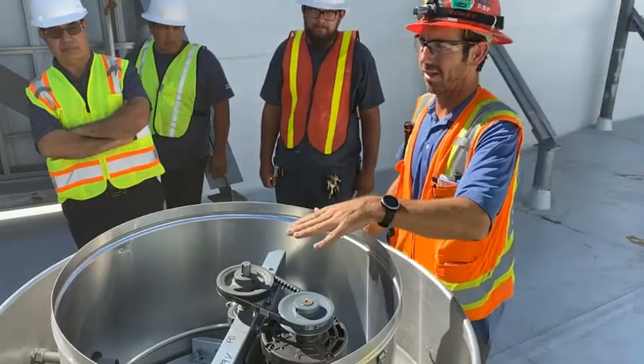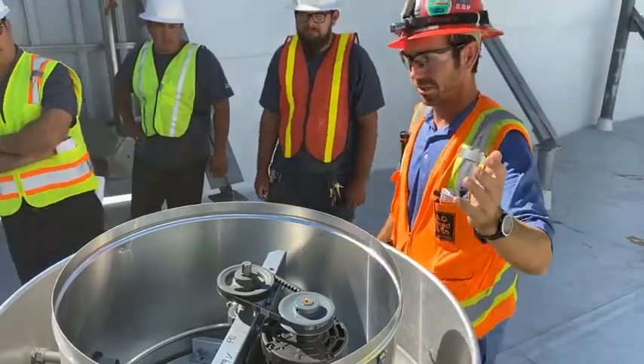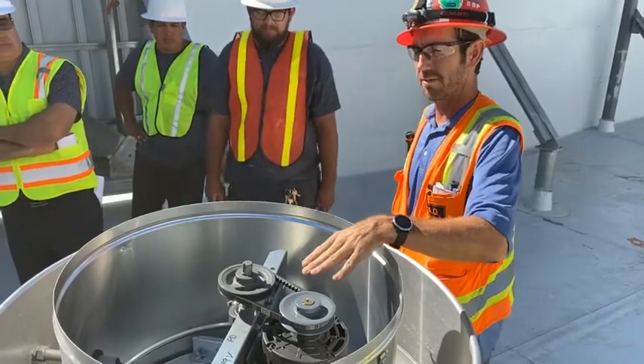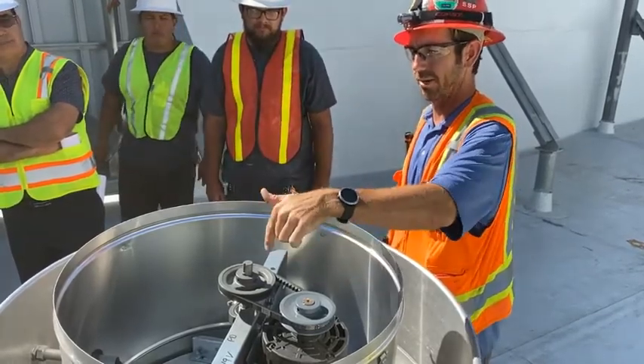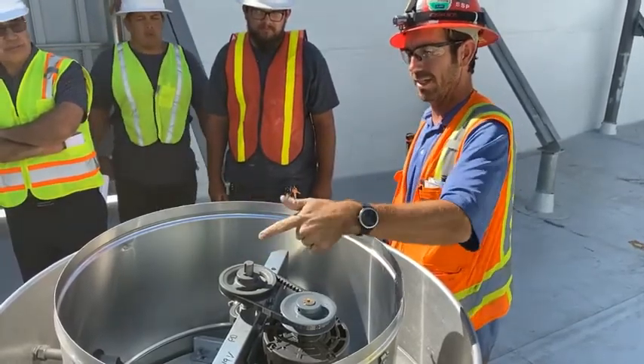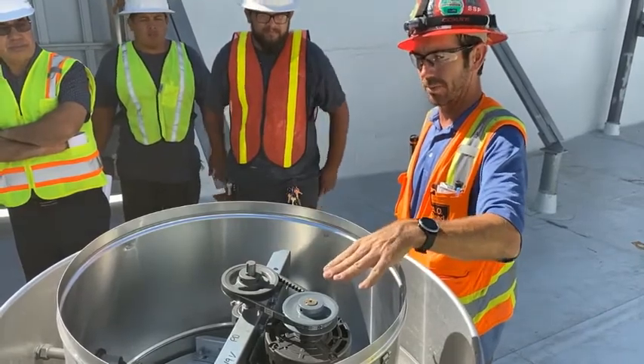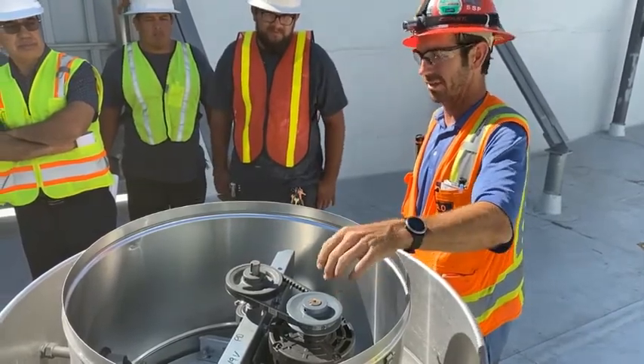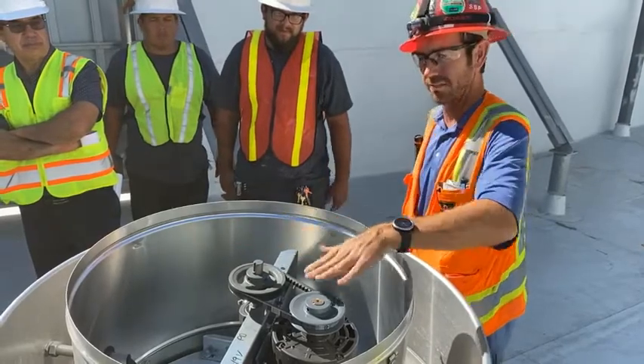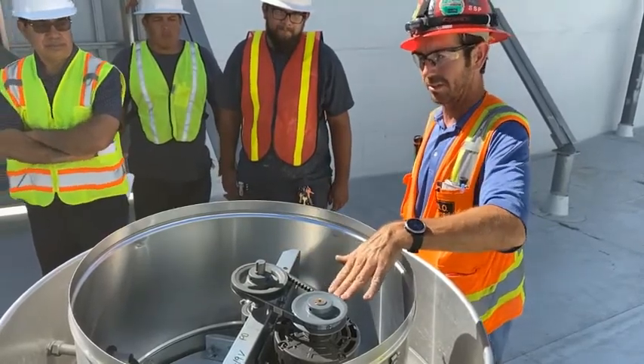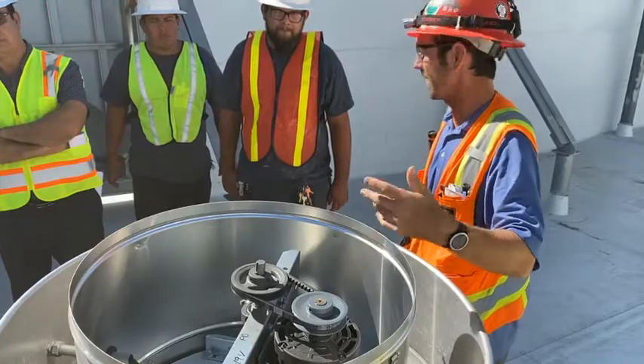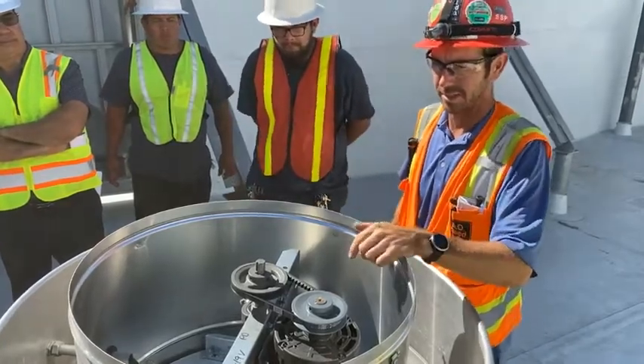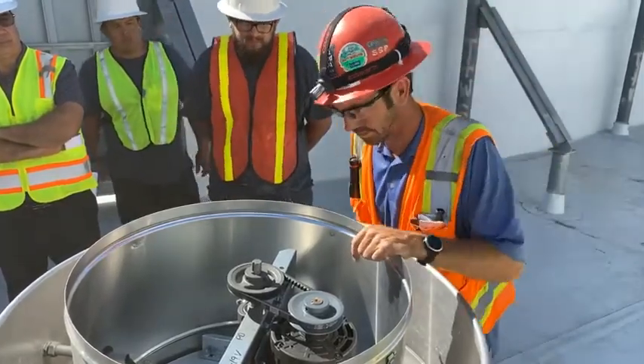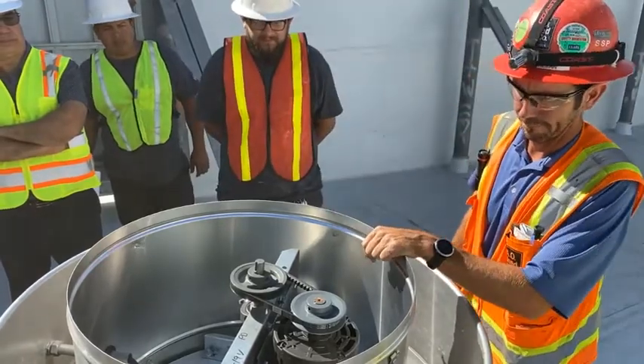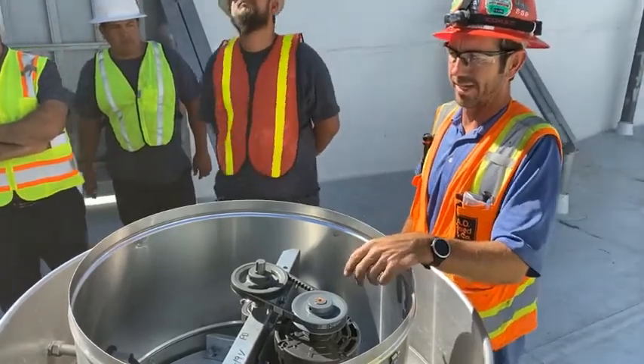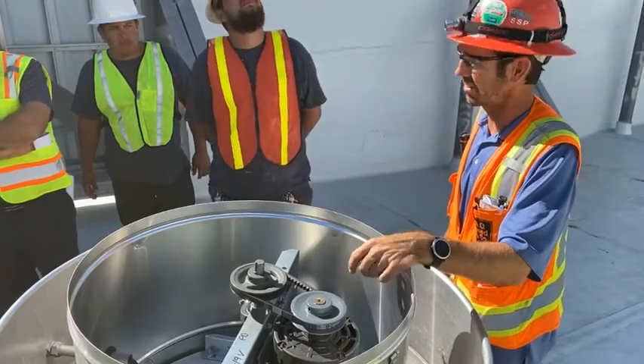Do you guys know how to check belt alignment? Just real quick, it is an adjustable sheave. Anytime you have an adjustable sheave, you need to compare the driven end, both sides, to each side of the drive end, because as you open the pulley, it's going to slide down, and you want to split the difference of the offset. If you just use the flat edge right here, and you have this thing super opened up, the alignment's going to go out, okay? Keep that in mind when you're doing the alignment and checking belt tension. You pretty much want the belt as tight as possible without squeaking on startup.